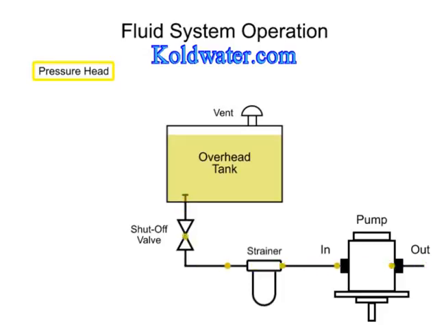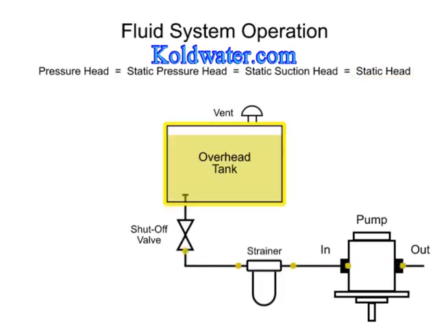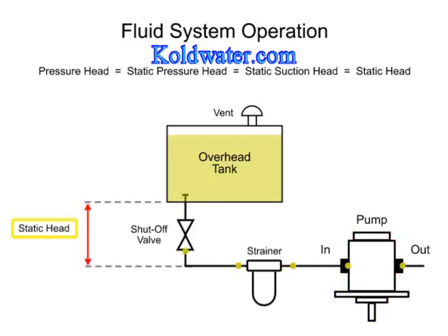Pressure head, also called static pressure head, static suction head, or static head, is created when the reservoir is placed at a height higher than the center line of the pump and is the measure of distance from the pump to the tank. This creates a positive inlet pressure and helps fluid flow to the pump.